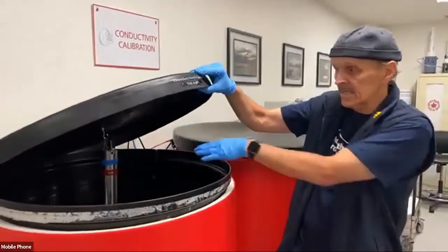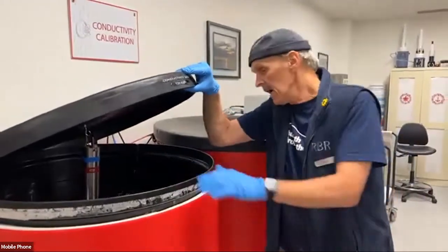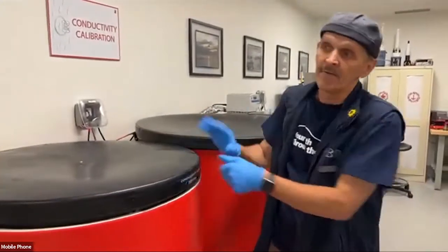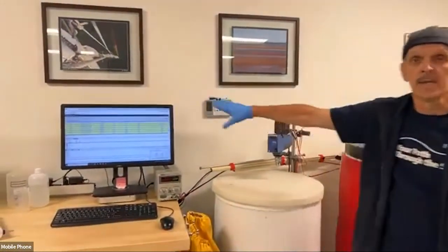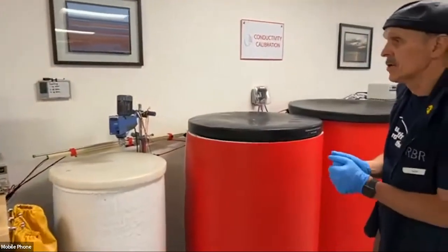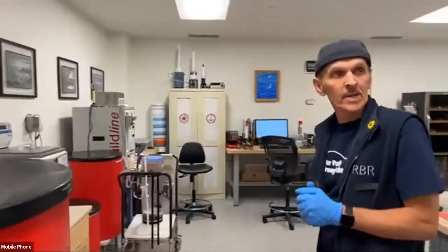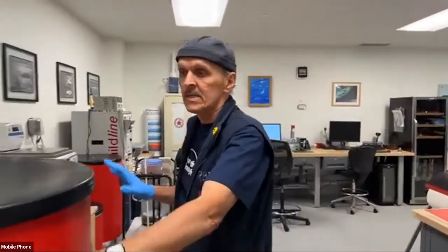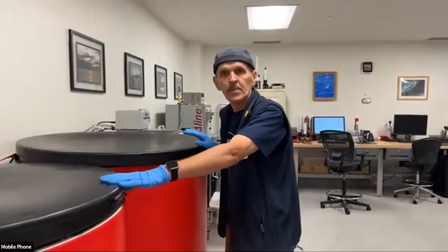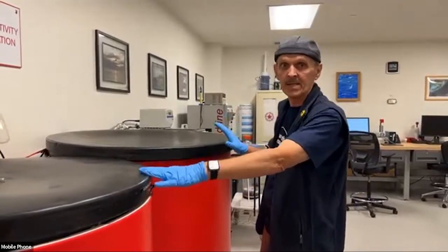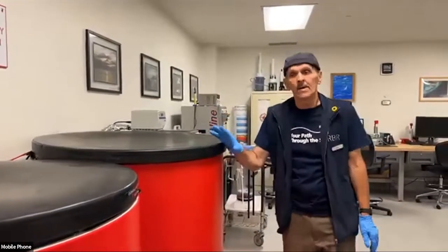That's also one of the baths for servicing instruments. It's just pumping and running, again close to 35 salinity, and we carefully monitor the state of salinity in the bath in our electronic notebook, and then use it for practical calibration. So a 10 degree step change gives us a number for temperature correction of cell geometry for a 10 degree step change, which is our temperature dependence correction.